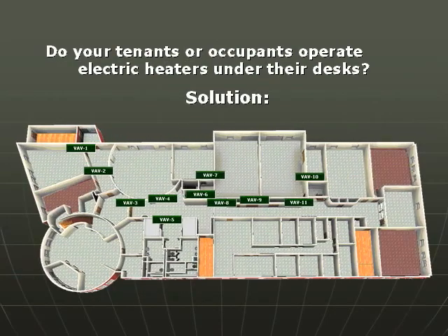By monitoring zone temperatures throughout the night, we've been able to identify excessive heat loads in the unoccupied periods, leading to the discovery of electric heaters that are left on, wasting energy and causing possible fire damage.